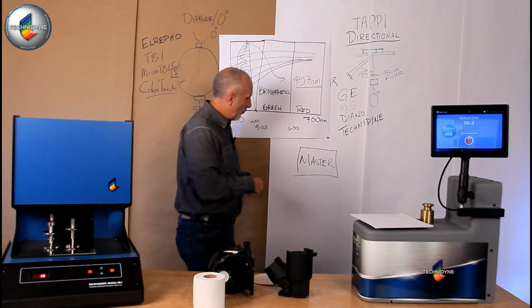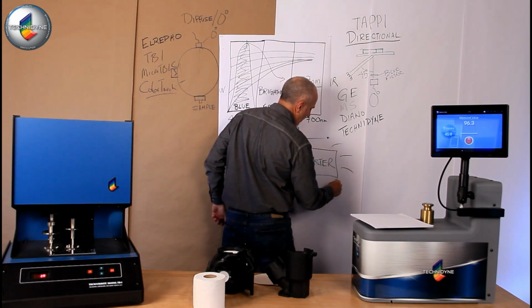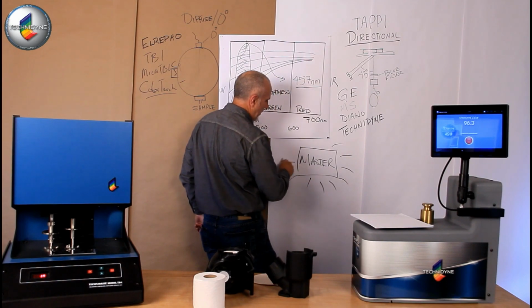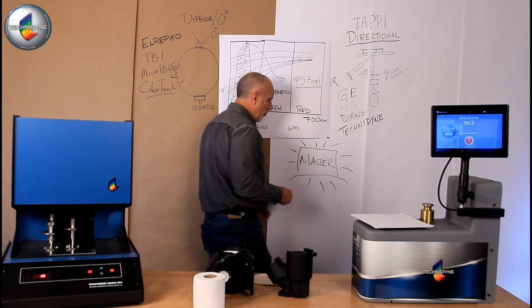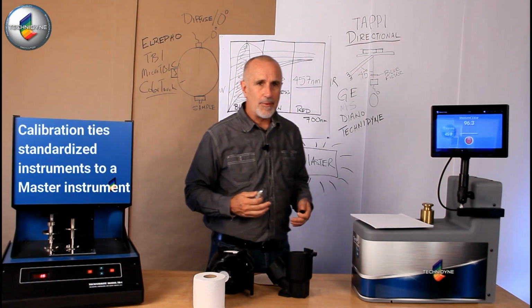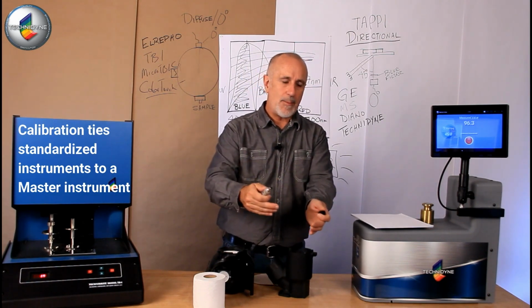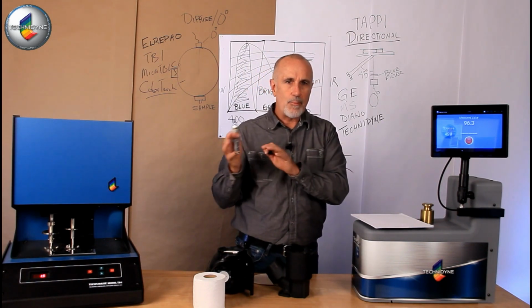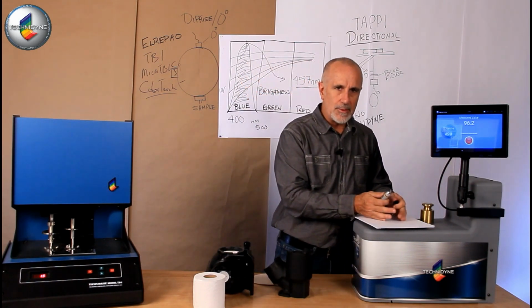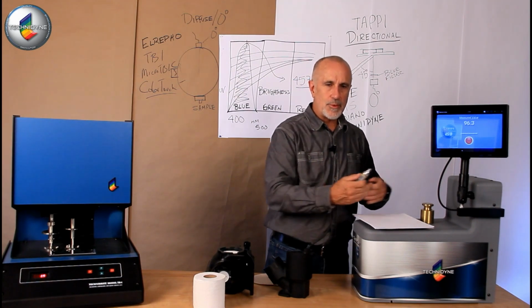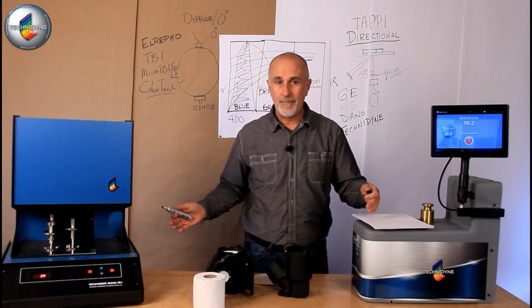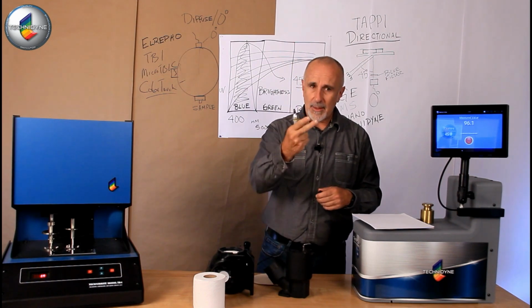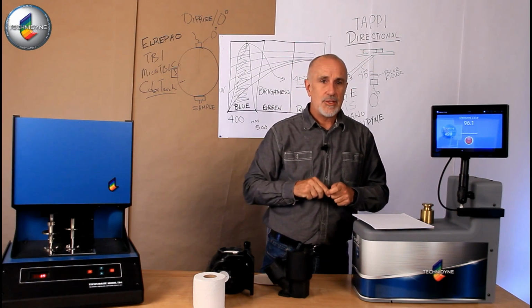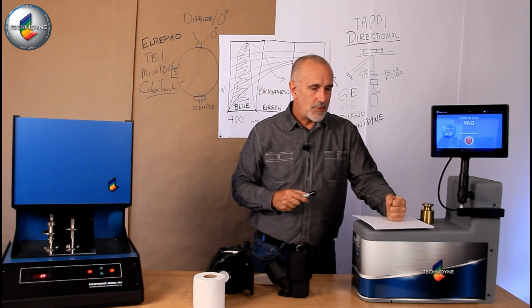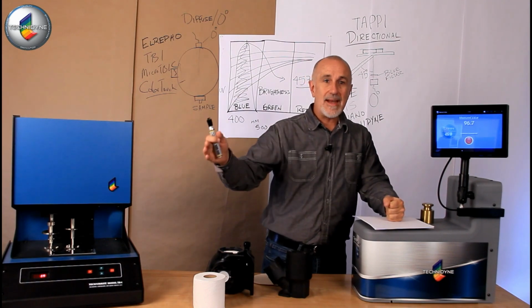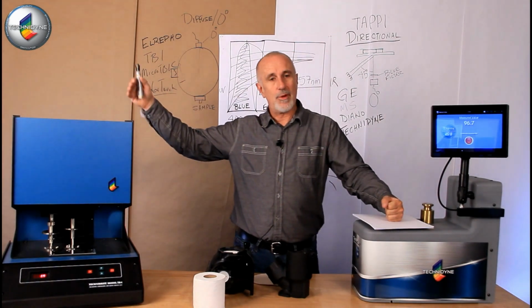And so if we are sending out samples to the industry from this master instrument, all reading similar paper, then we take those calibration papers onto our instruments. We're now bringing that calibration to this instrument. That gives us reproducibility from one instrument to another. That's one piece of it. The second piece is repeatability, so that if this reads 93 today, it's going to read 93 tomorrow, next month, next quarter, next year.